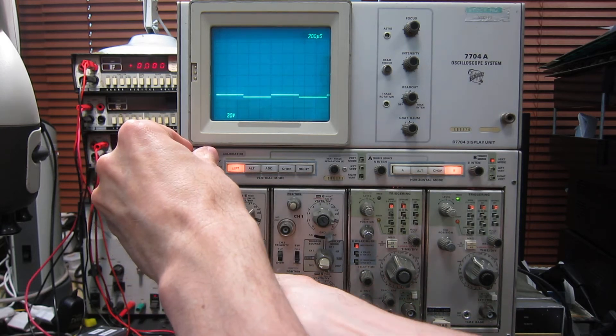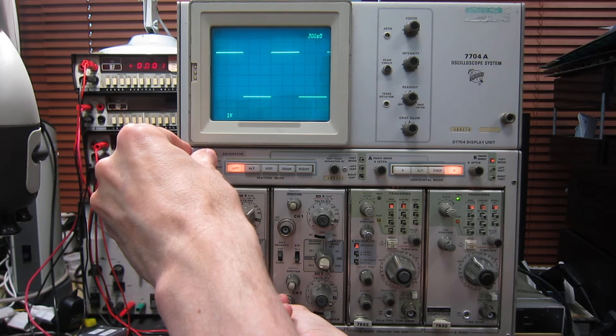And we can work through all of those attenuator settings. So these attenuators, although the 7A26 is notorious for dirty contacts, these ones have all been cleaned and serviced by me, so they've been good enough for me to use in my own lab.